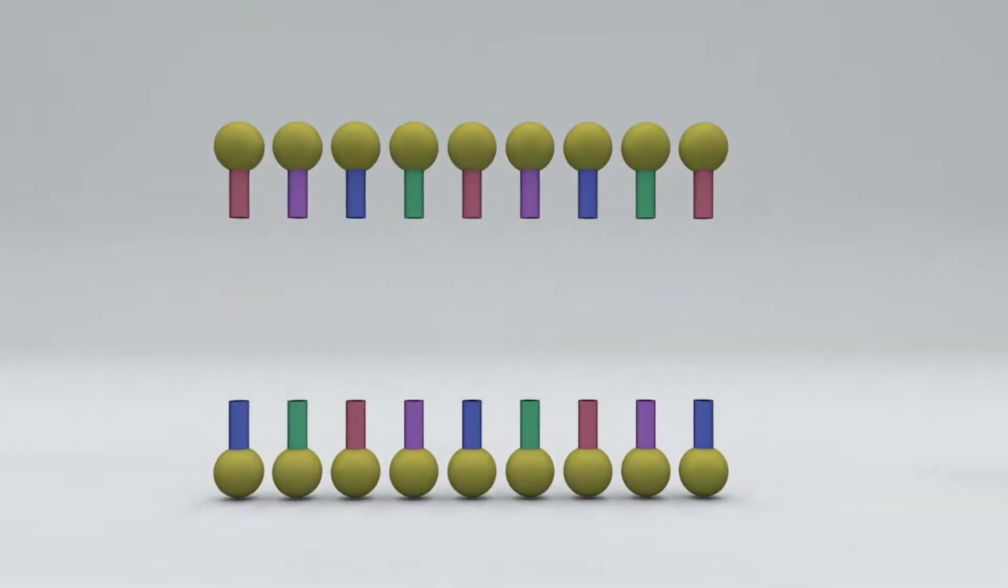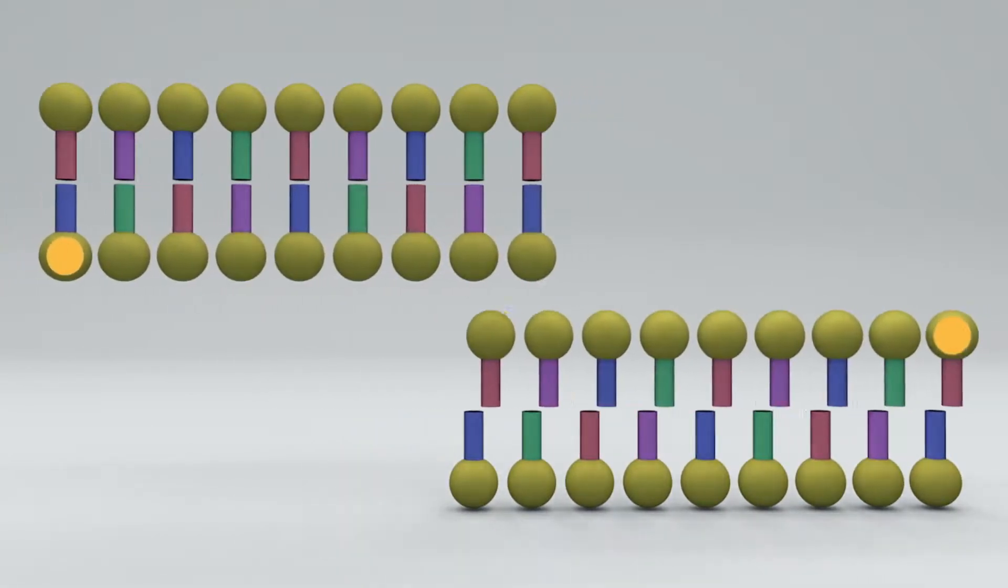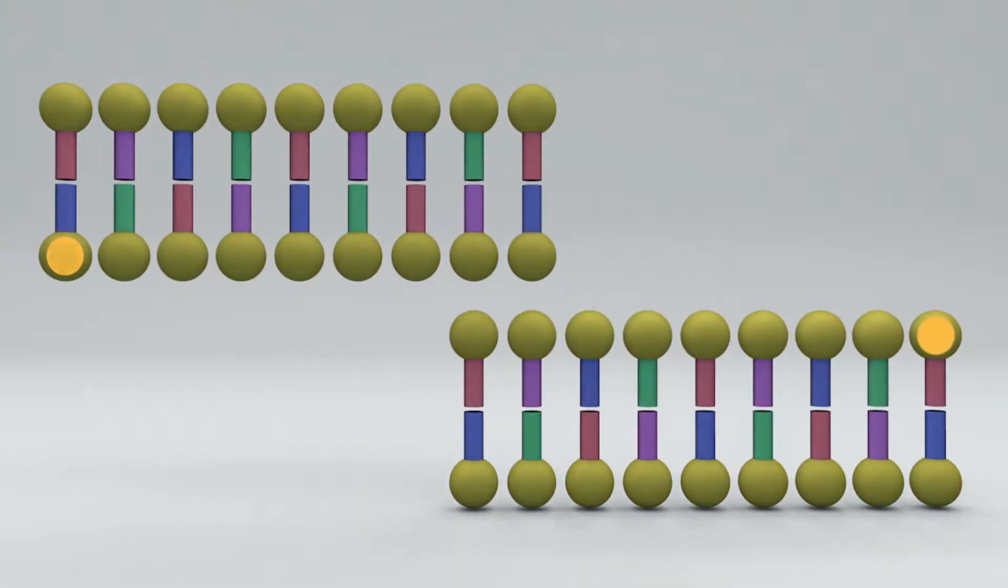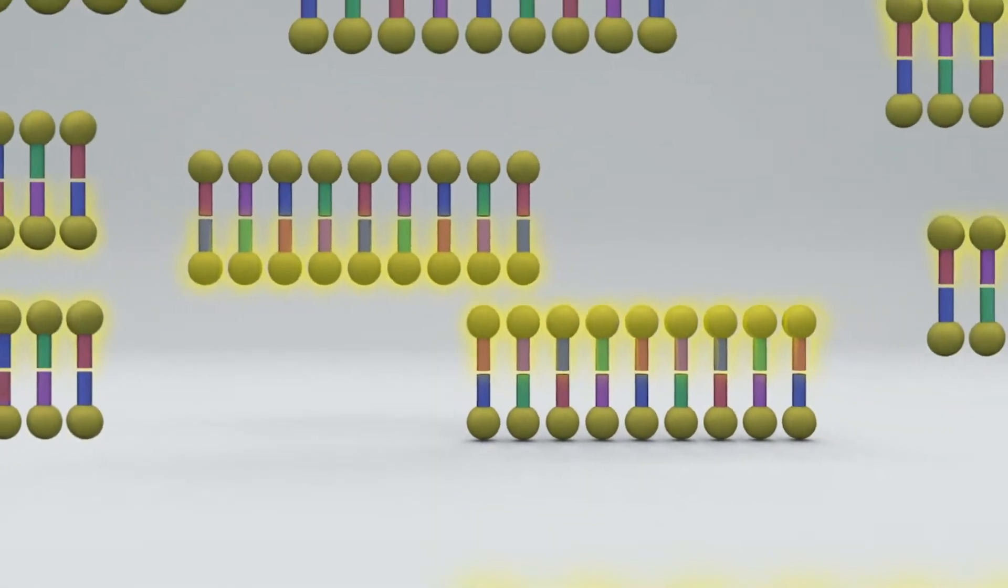Each time a new copy of the target DNA is created, a probe molecule binds to it, producing fluorescent light. The IDNow monitors the fluorescence during the test. If the fluorescence reaches a specific level, the sample is positive for that pathogen.